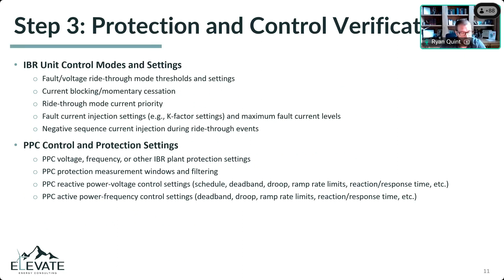We're looking at voltage, frequency. There's an exception for volts per hertz relay at the high side of the MPT. And again, checking the filtering, instantaneous trips, those types of things to make sure that all the curves are in alignment and compliant with the standard.